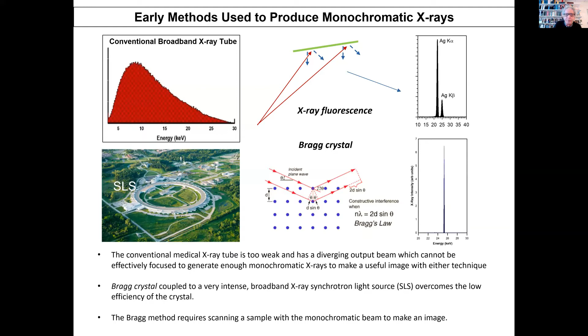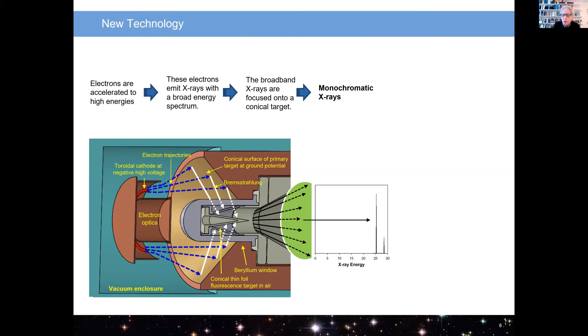So what we've developed is this new technology, and what I'm showing you here is an inverted conical anode target, which is irradiated by electrons through a high voltage potential. The broadband X-rays that are emitted from the circularly symmetric primary anode are then emitted into 2π, and a good fraction of them interact with a secondary target. This secondary target is compact. The best one we have designed so far is a thin foil of a metal or any material whose characteristic X-rays represent the monochromatic X-rays that one would like to use for the imaging.